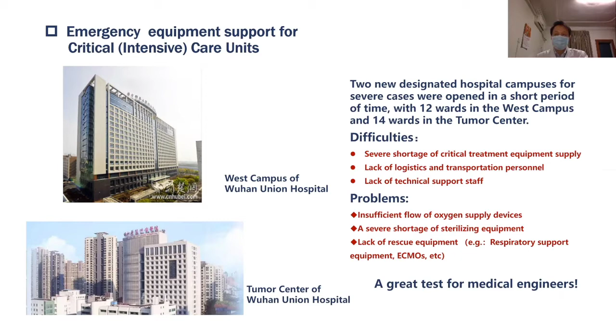In addition, we also met many other problems, like the oxygen support equipment failed to generate required oxygen flow. Since most of the patients with COVID-19 needed to use a ventilator for special oxygen treatment, the demand for oxygen grew as high as dozens of times the normal demand, while some ICUs were converted from ordinary wards, whose oxygen supply system could not meet the actual demand, which caused a drop of oxygen pressure and low flow rate. In addition, the ward saw serious shortage of disinfection equipment. In order to reduce the infection risk of medical personnel in the wards, a large number of disinfection equipment needed to be configured. Life support equipment, such as ventilators and ECMO, were also in shortage.